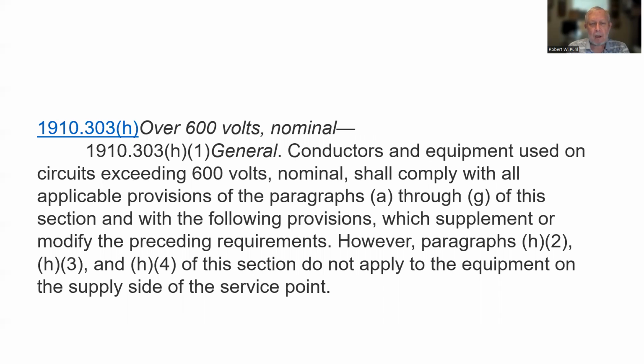Now this is over 600 volts nominal. General, conductors and equipment used on circuits exceeding 600 volts, this is called high voltage, shall comply with all applicable provisions of paragraphs A through G of this section, and with the following provisions which supplement or modify the preceding requirements. In other words, everything through A through G, which we've already talked about, they have to do that. However, paragraphs H2, 3, and 4 of this section do not apply to the equipment on the supply side of the service point.